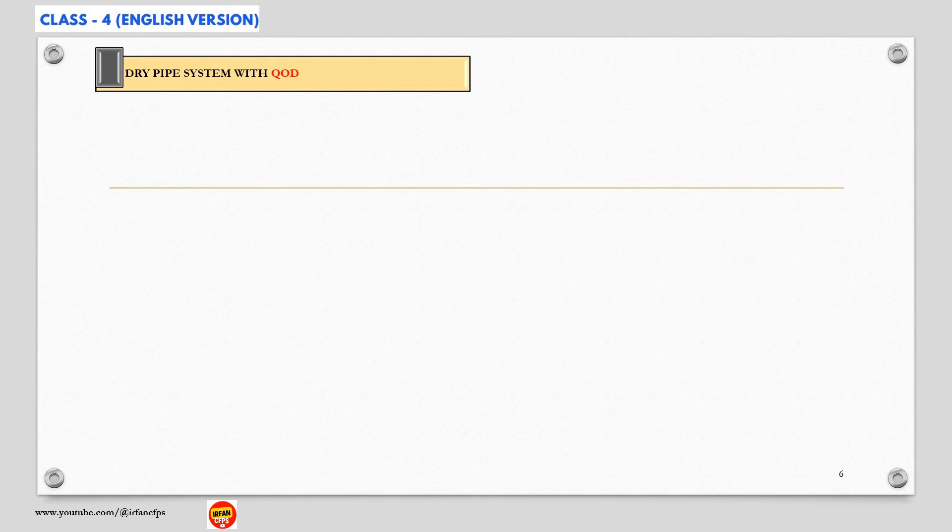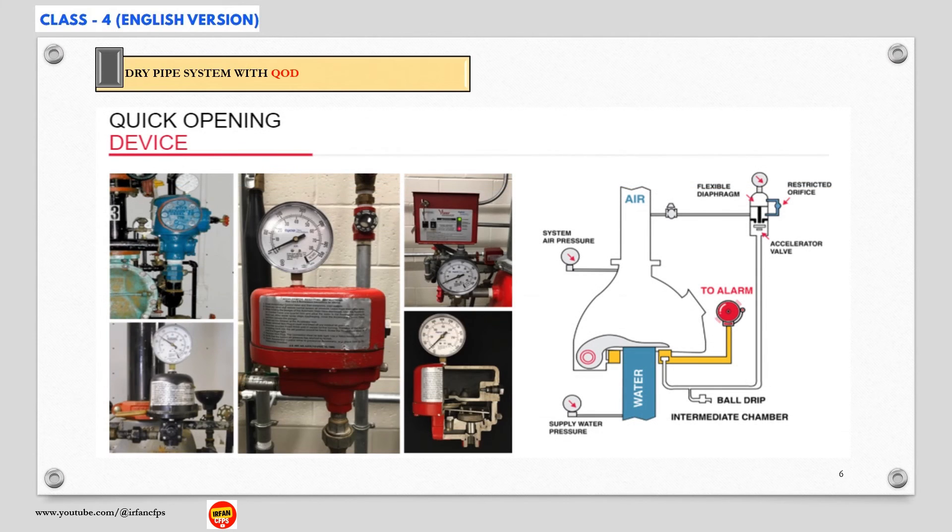Dry pipe systems operate on a differential principle in which the system is equipped with a differential valve that allows lower air pressure to hold back higher water pressure. This system is installed with a quick opening device called accelerator.